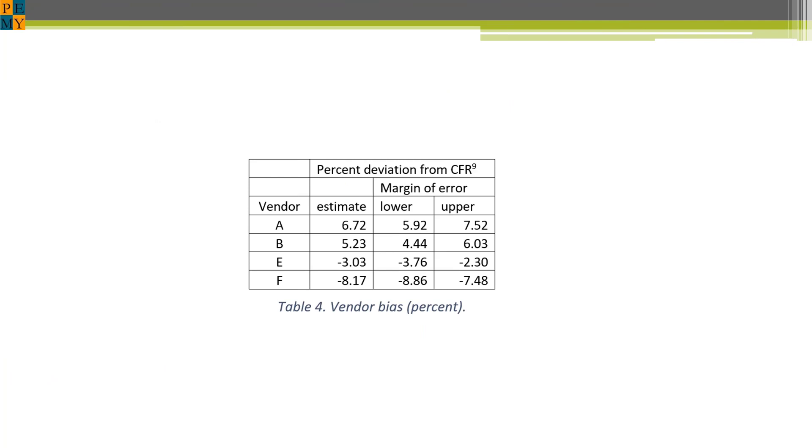This table shows the deviation of the four vendors from the consensus flow rate and is the basis of our claim that there are significant differences in accuracies of at least some of the vendors in the way that they do flow measurement.